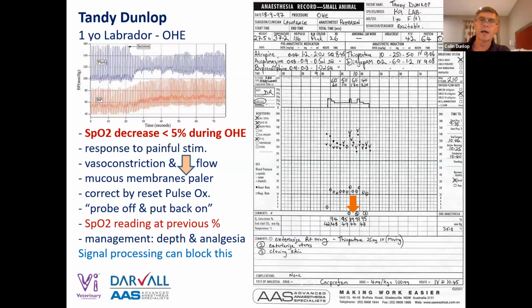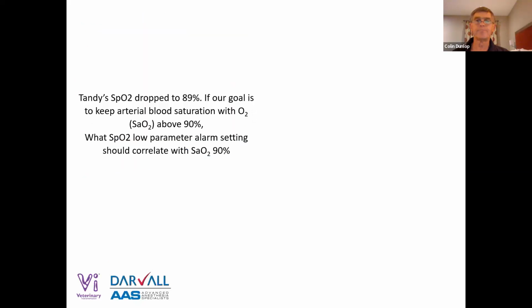So if you do that, and there was less blood flow in that tissue than originally, the machine should reset itself and give you the same saturation reading it was giving before. And you can see that that's what's happened in this animal. One of the problems with new pulse oximeter technology is that it's designed to dampen out that response. That's a very good response to see in anesthesia because it tells us something about blood flow and how our animal's responding to painful stimulation. But a lot of new pulse oximeter technology tries to process the signal and damp that out.